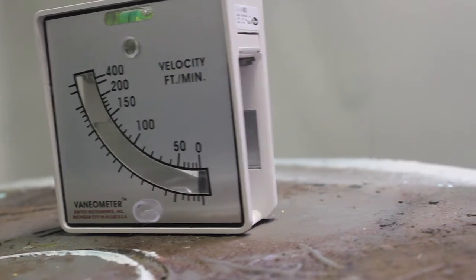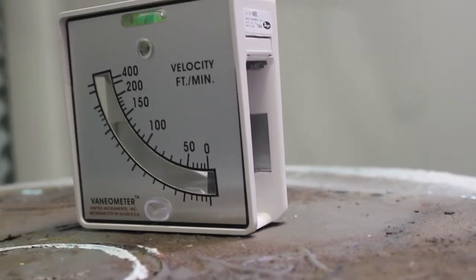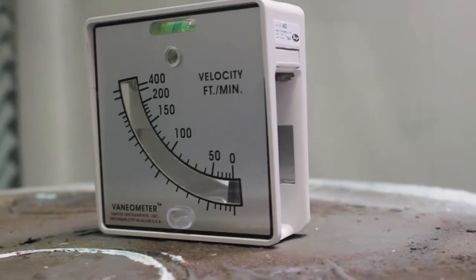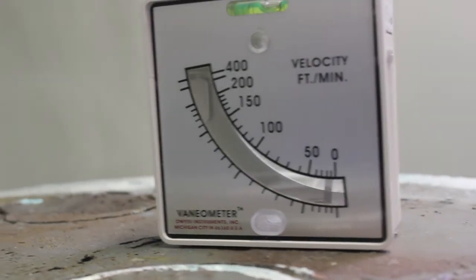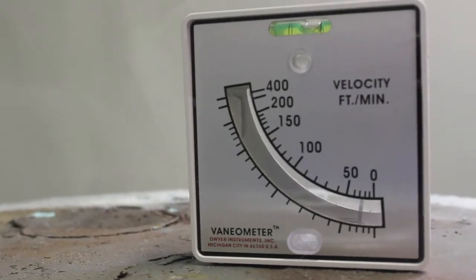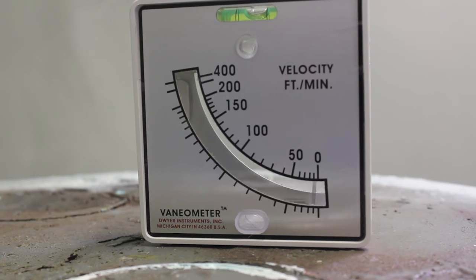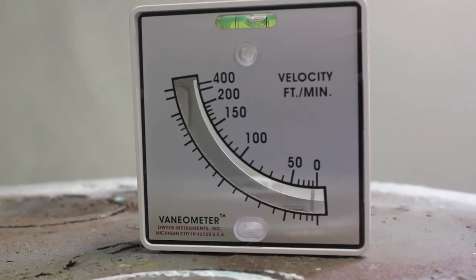After that, you can check your fan, your exhaust fan, to determine if there's excessive paint buildup on the blade, or maybe the fan isn't drawing a proper amount of amps or power to properly deliver the volume of air out of the booth that it should.